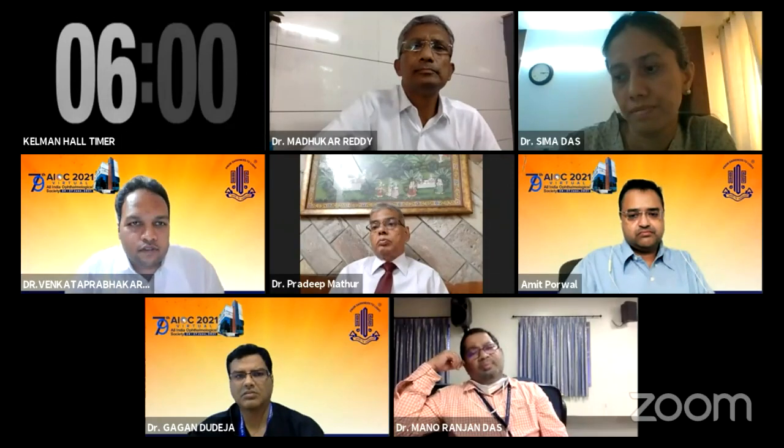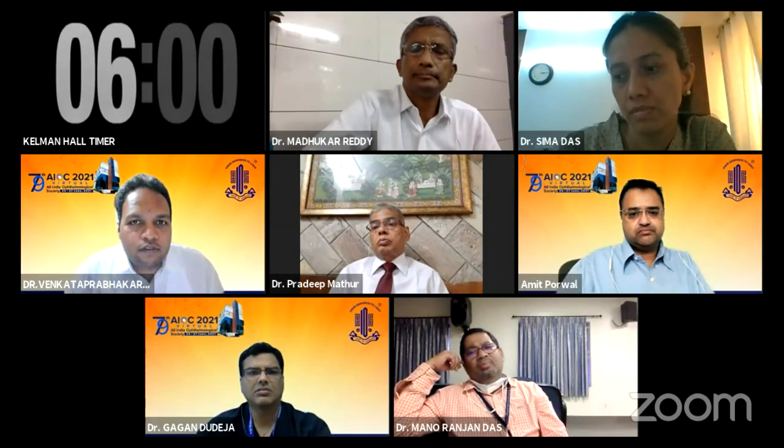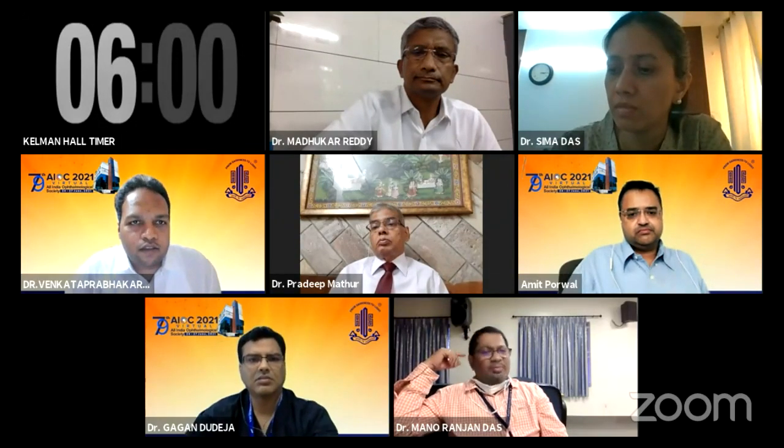Why did you keep those dialing holes? Because you can just push the hydrophilic material, you can just push the lens inside. There's no need for those dialing holes. So again, that is mainly to aspirate the visco behind the lens, sir, because it's a concave lens, and the visco will get trapped behind the lens. So we need a hole to aspirate it.